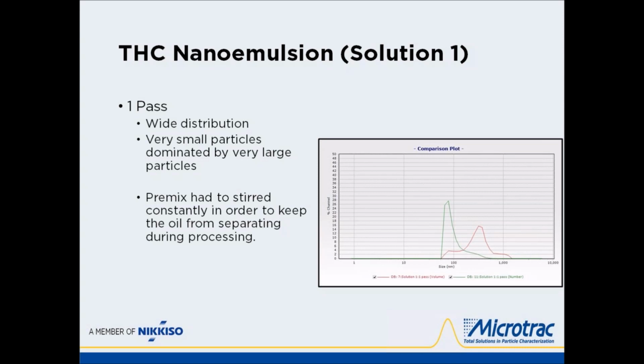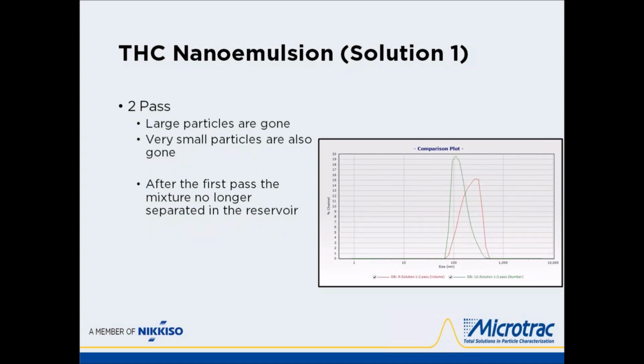Again, this is before the first pass, it had to be stirred constantly to keep it from separating. Moving into the second pass, you can see that all of the large particles are gone, but unfortunately, some of the very tiny particles are gone too. But we are trending toward uniformity because the volume distribution and the number distribution are starting to get closer to each other. And after the first pass, it didn't have to be stirred anymore because it was a much more stable solution. It was not going to separate after that point.